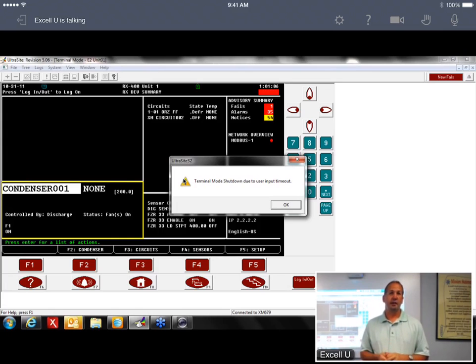I know at one store we just made rack 1 have its own loop, and rack 2 had its own loop, and then on the board inside the E2, that's where we connect them. That's correct. That store was a little different because they had 2 racks per controller, and they were old legacy E2s. They're putting the new controllers in because the old ones are too slow.